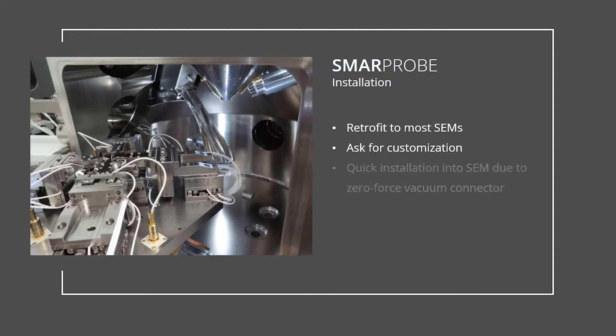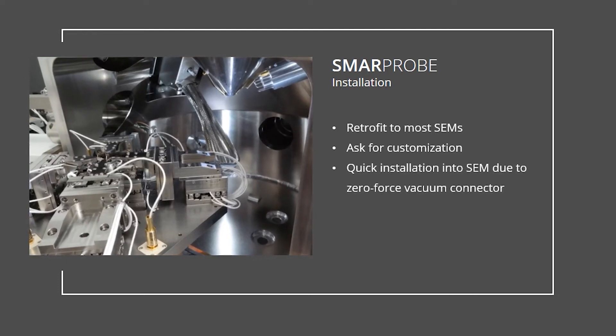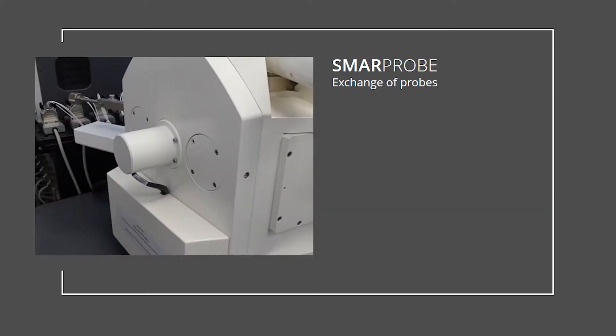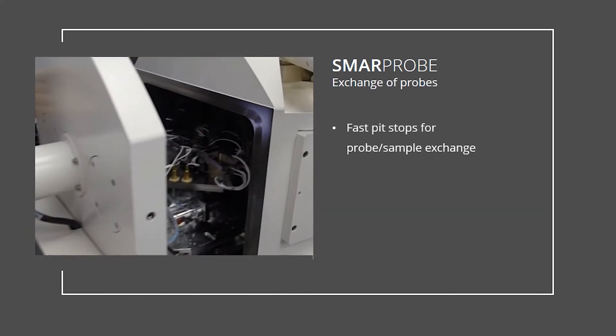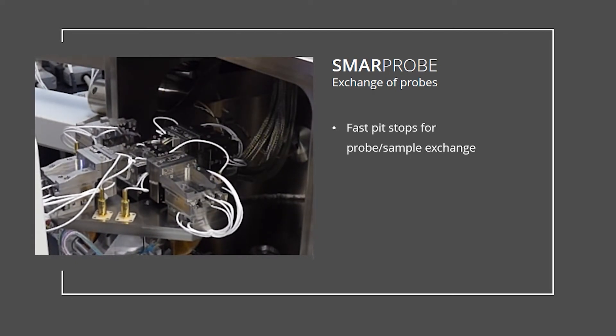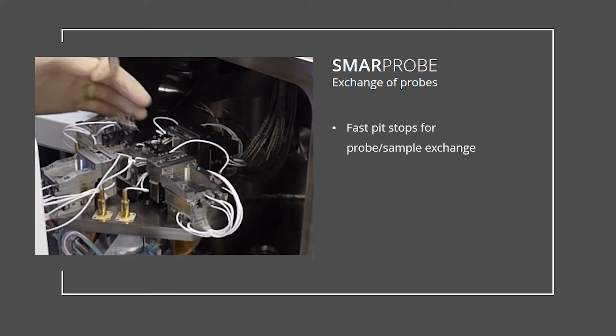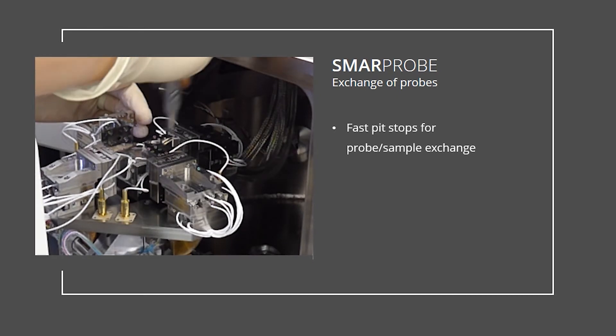The unique zero-force vacuum connector guarantees quick installation into the electron microscope or into an atmospheric setup for microprobing. The exchange of probes is facilitated by predefined movement macros. The to-be-exchanged probe is lifted by the manipulator for easy access.